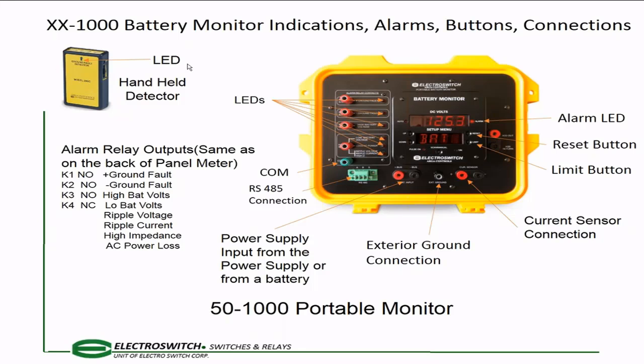This up on the upper left is a handheld detector that is a $230 component that can be used to find the ground in case you have an actual ground occurring on the DC bus system. What we have is a pulsar. There's a little pulsar, and I think further down in another presentation, you'll see that the pulsar's on. So that's sending out a little ripple current across the battery DC system. And if you have a ground, you take that handheld detector, turn it on, and that will help you locate the ground. And then you would go through an isolation process, if it's a bundle cable, to find out which cable that would be.